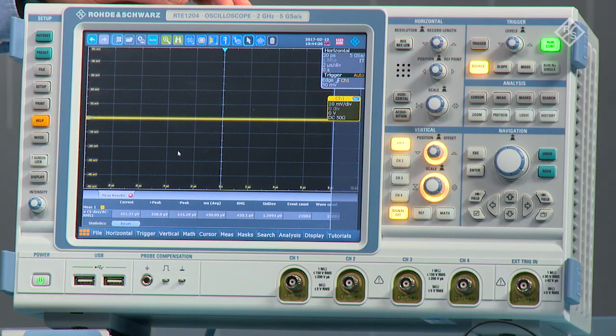First, it's always best to start with a scope that has low noise. Your scope will never take a more precise measurement than the amount of noise that it has on it. How do you determine how much noise your scope has? It's very easy. Here I've disconnected all of the inputs from the front of the scope and I've turned on a noise measurement. At 10 millivolts per division and 2 gigahertz bandwidth that this RTE has, I can quickly determine how much noise I have. In this case, a little less than half of a millivolt, which is impressive for scopes of this bandwidth and vertical setting.